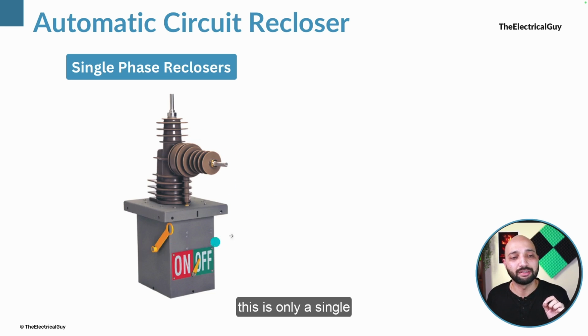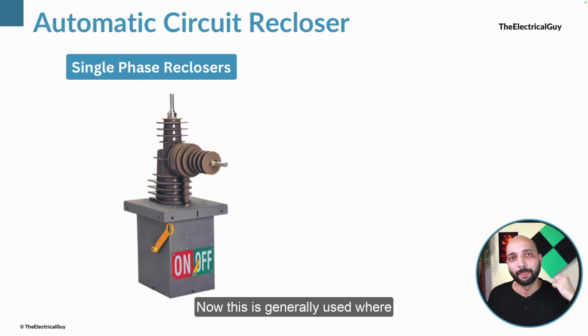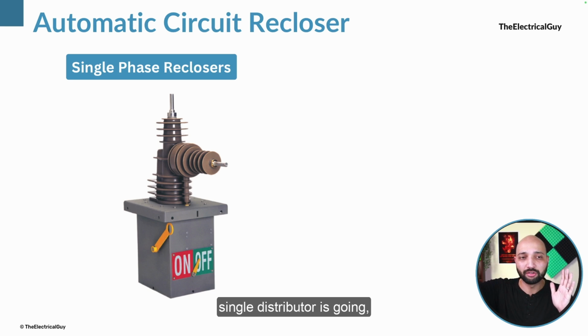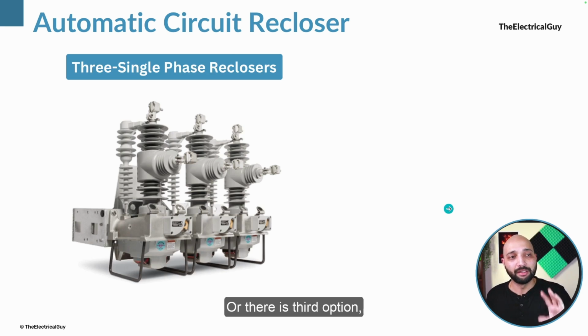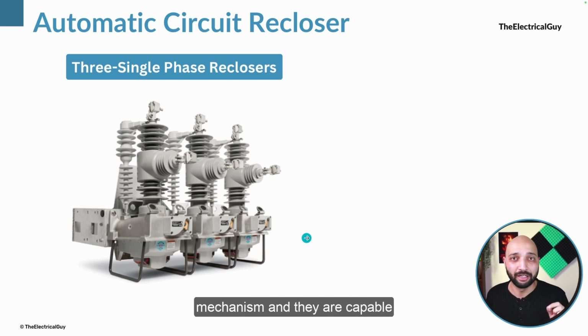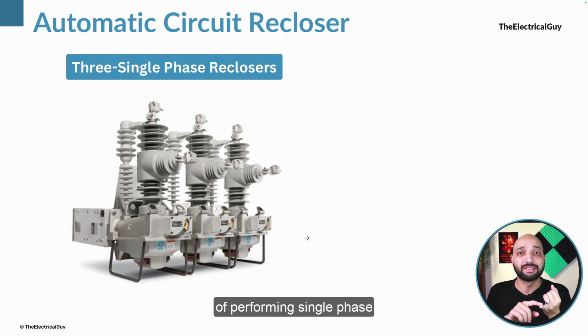There is one more option, which is a single phase recloser. This is only a single phase item, meaning only a single phase will be operated. This is generally used where taps are taken from a three phase feeder. If only a single feeder, a single distributor is going, then a single phase recloser will be used there. Or there is a third option, which is three single phase reclosers, which means that every phase will have its own dedicated mechanism and they are capable of performing single phase reclosing and also three phase reclosing at the same time. So those are the different options available.